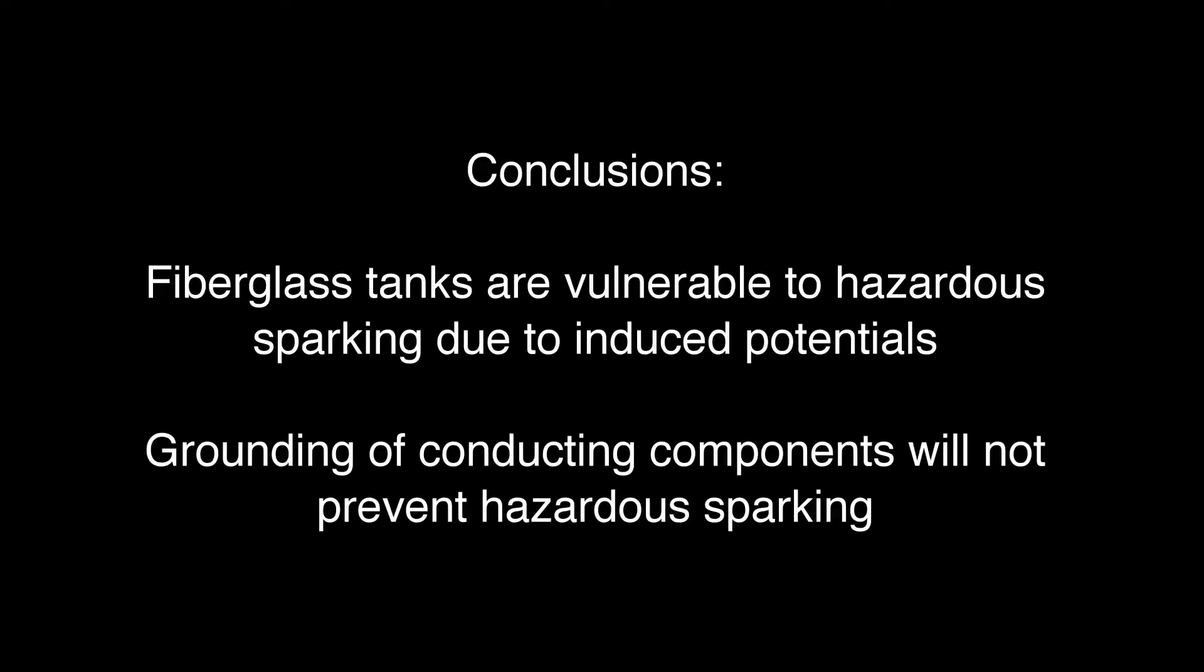Conducting components inside fiberglass tanks are vulnerable to sparking due to induced potentials. Grounding of the conducting components, while recommended for other reasons, does not prevent sparking due to induced potentials.